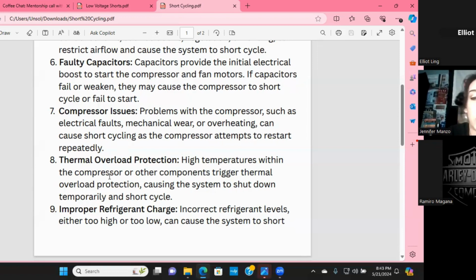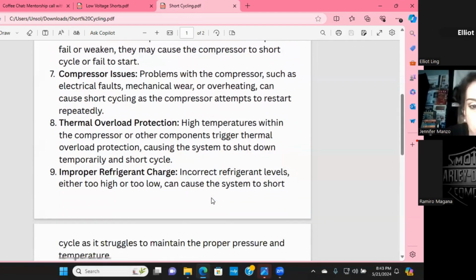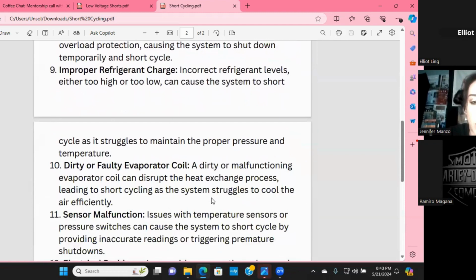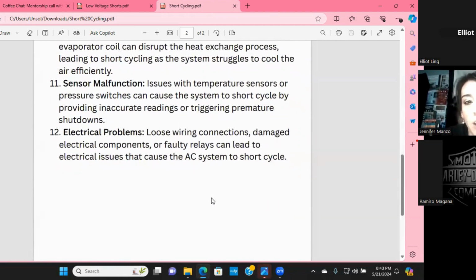So when high temperatures within the compressor or other components trigger the thermal overload protection, it causes the system to shut down temporarily and short cycle. This will happen, but it could also shut it down for a very, very long time, and the house is going to get a super load on it, which you also don't want. And then we've already gone over charge, and then the evaporator coil. Sensor malfunctions happen all the time. We end up with bad outdoor ambient sensors telling the thermostat that the temperature is wrong, and it just continues to kick on and kick off. That happens a lot. Make sure that you're testing those sensors, you guys.